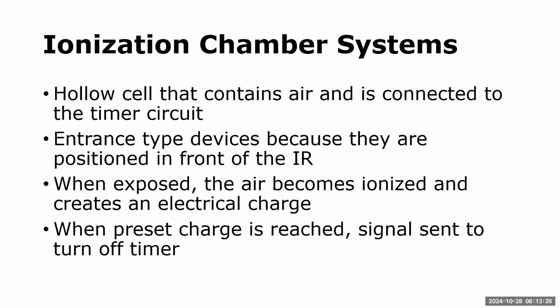So when that chamber is exposed, the air becomes ionized and creates that electrical charge. And again, do you see how many times we've already said this statement? When that preset charge is reached, then it sends the signal to turn off the timer. So it's all related to how long it takes for that preset charge to be met. That determines how long your exposure time actually will be.